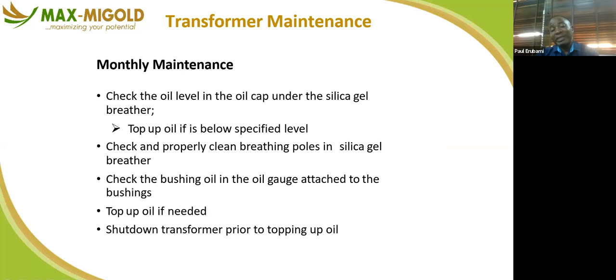So these are the monthly maintenance tasks on your transformer. Check the oil level. Oil is very key in any form of machine. So you check the oil and top up if it is below the specific level; there's a value that the oil must not go below. You ensure that it maintains the required level. You have the silica gel as well. Check the breather and check if it's blocked. If it's blocked, you clean it up and remove the particles.